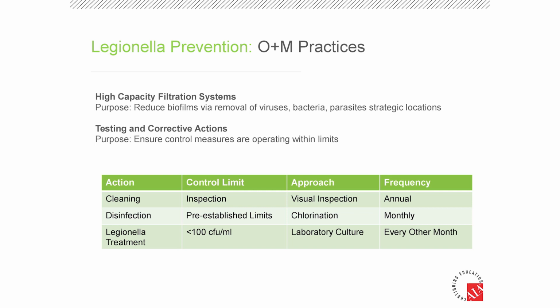That's typically a monthly disinfection program, but you can do it more often if you'd like - maybe every 3 weeks to be safe. It's not much additional cost, but it gives peace of mind. Legionella treatment should keep levels below 100 colony forming units per milliliter of the sample.